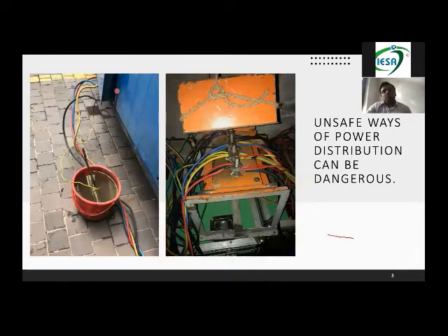If you are using maybe a 250 kVA genset, to give you an example, in Bombay, where I stay, the genset guy says that they only give 120 kilowatts of power from a 250 kVA genset. So for a 250 kVA genset, we are using 95 square mm rubber copper cable, because that can take a load of that many amps. According to that same wire, the half size, maybe like a 50 square mm, the neutral wire has to be there, and the same wire has to be there for the earthing also. Why? I'll just give you an example. Why is earthing important?